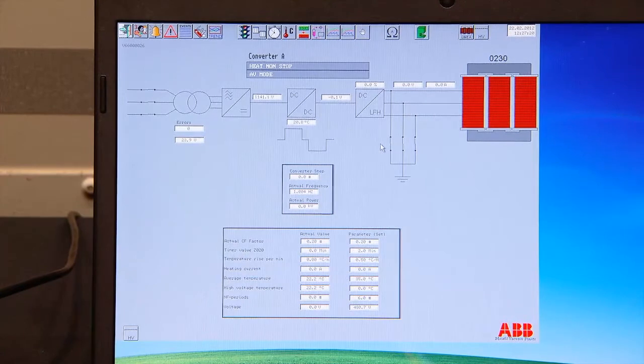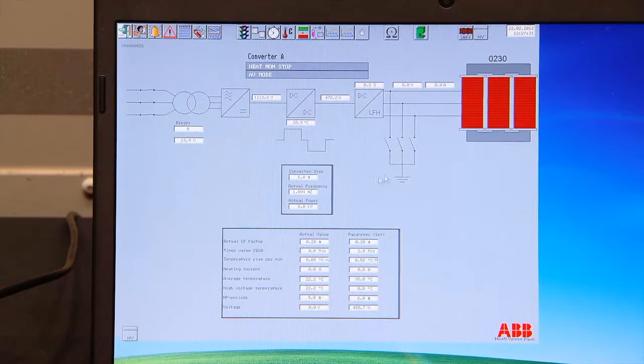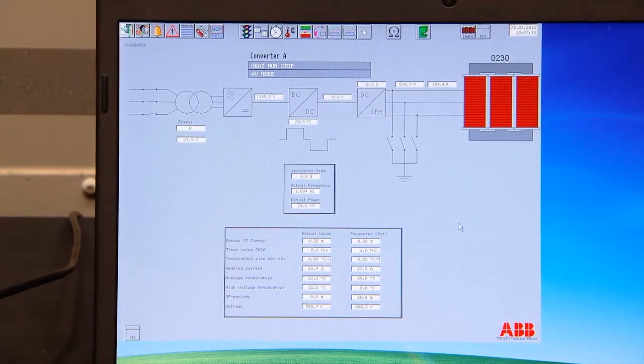Now, because we are not running yet, we have charged the DC link, trying to equalize the pressure, and now we're running. I got it. What he's doing now initially is taking 6 cycles of 1 hertz to just check that the voltage level is correct, and then he will continue running now for 20 cycles continuously.